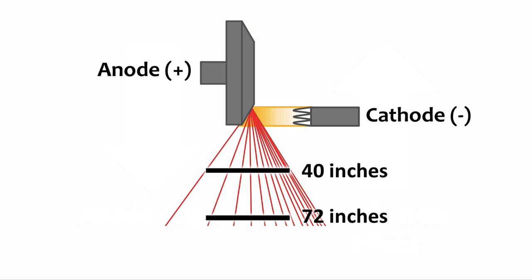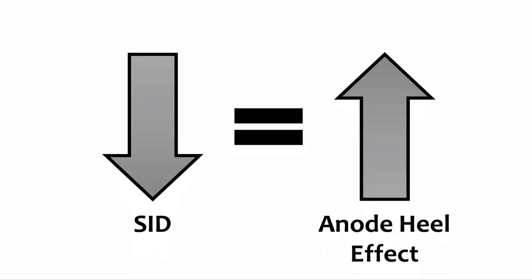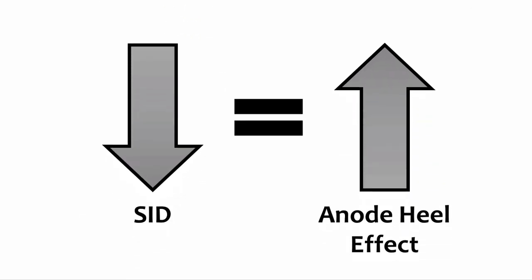Changes in SID also affect the extent of the anode heel effect. Decreasing or shortening the SID increases the heel effect. Shortening the distance causes the receptor to get exposed to more of the low intensity beam on the anode side and more of the high intensity beam on the cathode side, resulting in an increased difference in intensity. The relationship between SID and the heel effect is inverse: as the SID decreases, the anode heel effect increases.